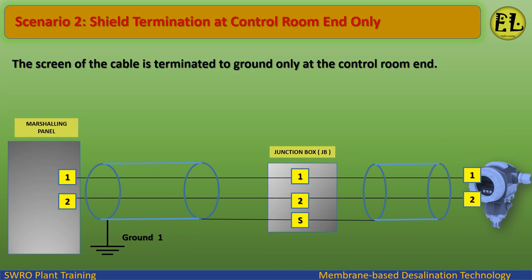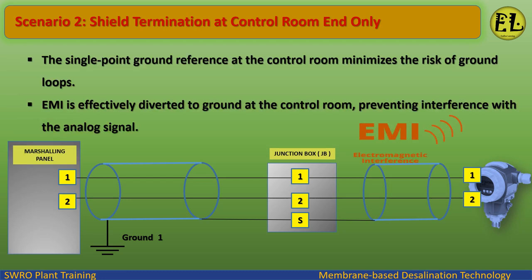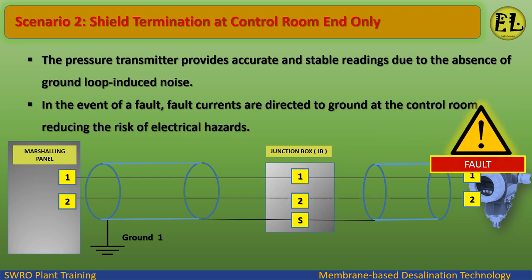Scenario 2: Shield termination at control room end only. The screen of the cable is terminated to ground only at the control room end. The single point ground reference at the control room minimizes the risk of ground loops. EMI is effectively diverted to ground at the control room, preventing interference with the analog signal. The pressure transmitter provides accurate and stable readings due to the absence of ground loop induced noise.